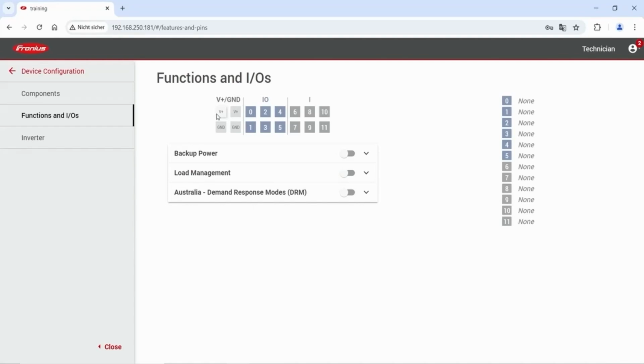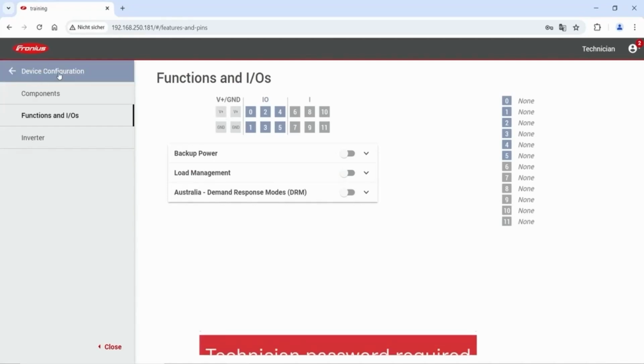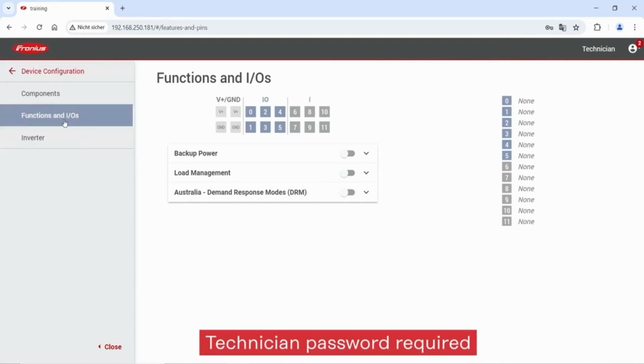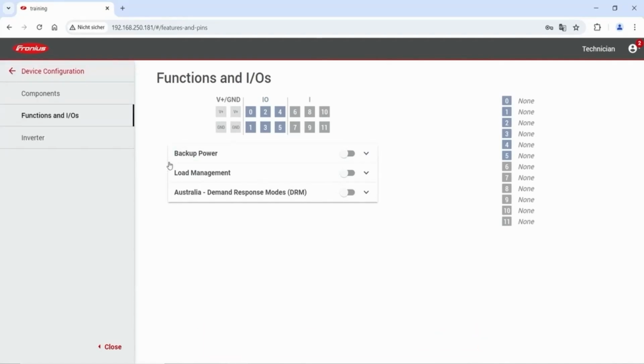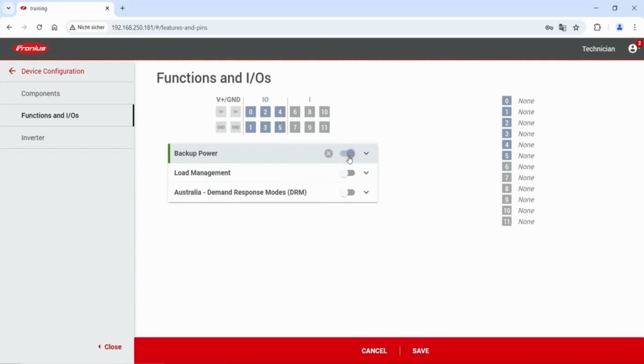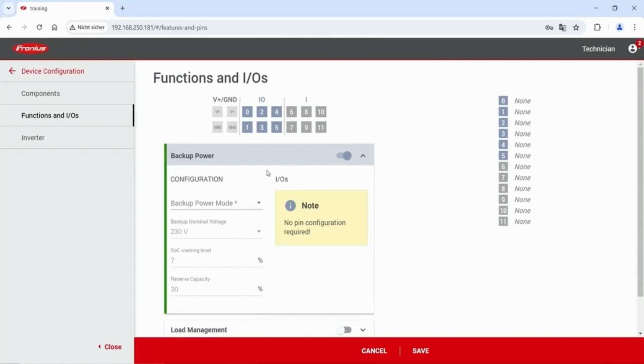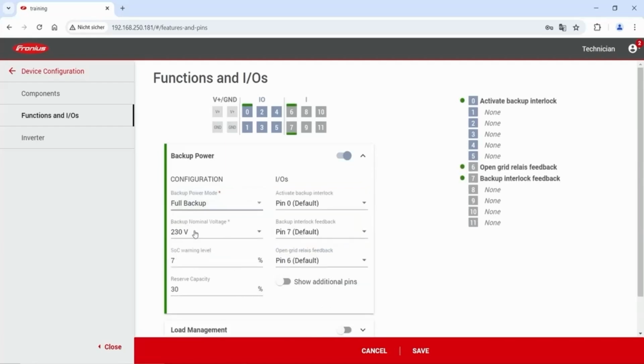For the configuration of the backup power functionality, we start in the web interface of the Fronius GEN24 Plus with device configuration and functions and IOs. In this section you will find the point backup power, and you can activate this functionality with this little switch here. In the drop-down menu you can now configure your delivered solution. So in this case we are configuring full backup. And after that we can set the nominal backup power voltage, in our case 230 volts. And last but not least, the SOC warning level as well as the reserved capacity can be set.